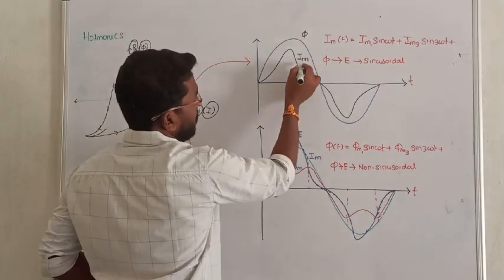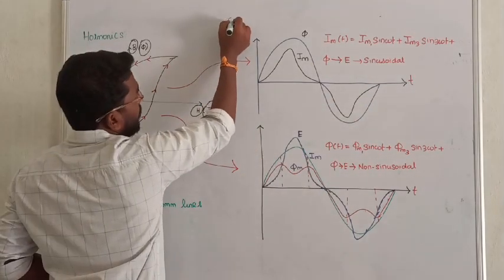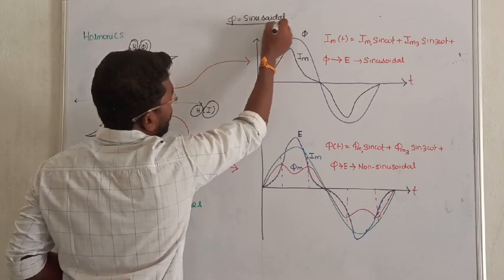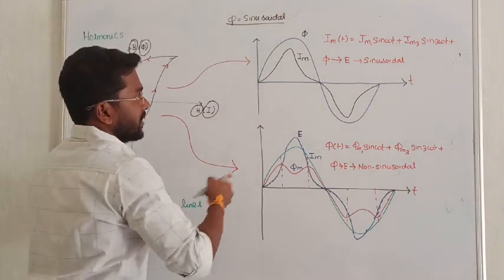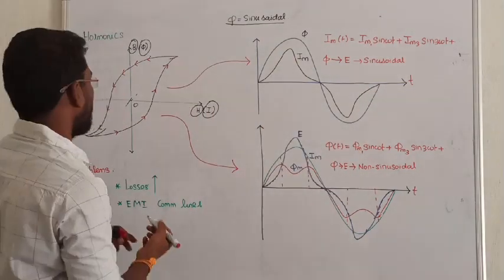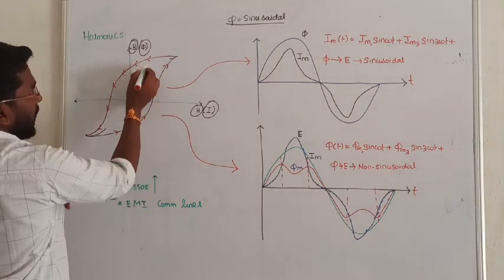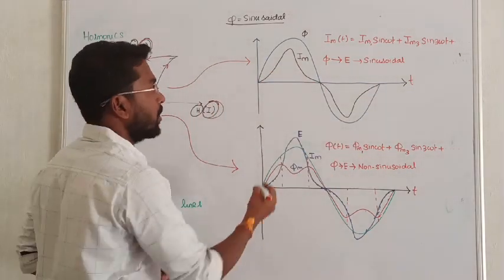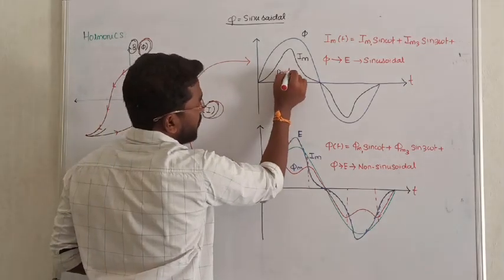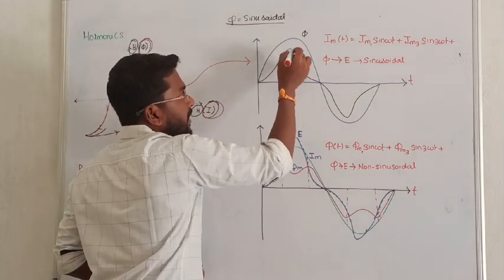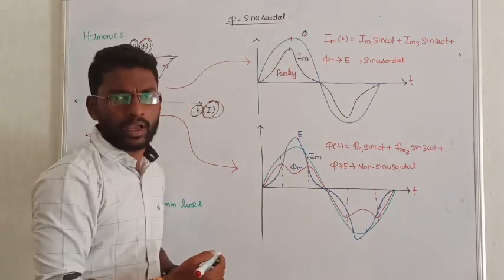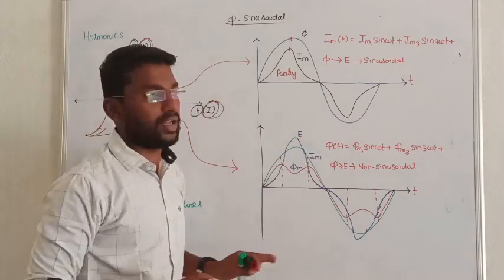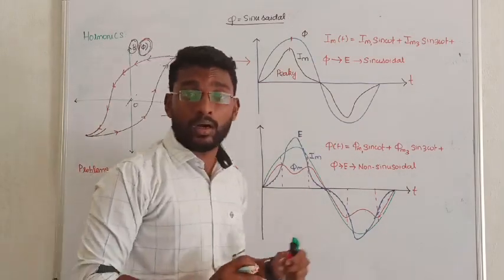Now I am going to draw the waveform between magnetizing current and time. Case number one: I am assuming the value of flux is sinusoidal. The first waveform in clear blue color indicates that the flux is purely sinusoidal. Using the flux-versus-current BH curve, you can derive the magnetizing current. The magnetizing current is peaky in nature. Even when the flux reaches its maximum value, the magnetizing current is not purely sinusoidal.